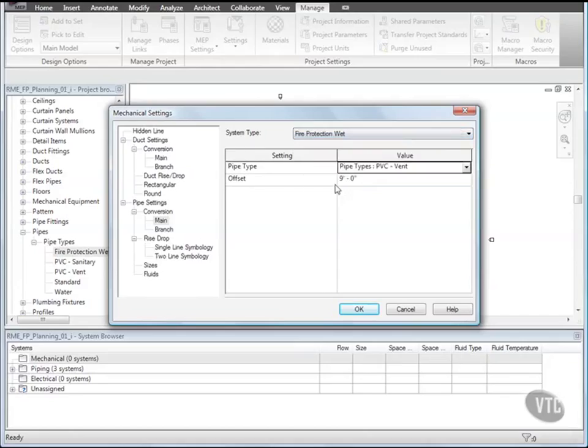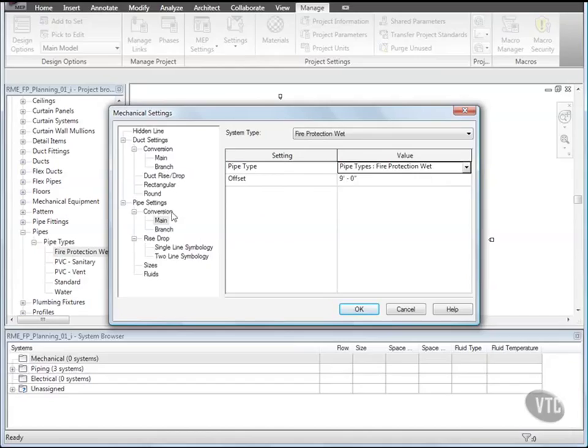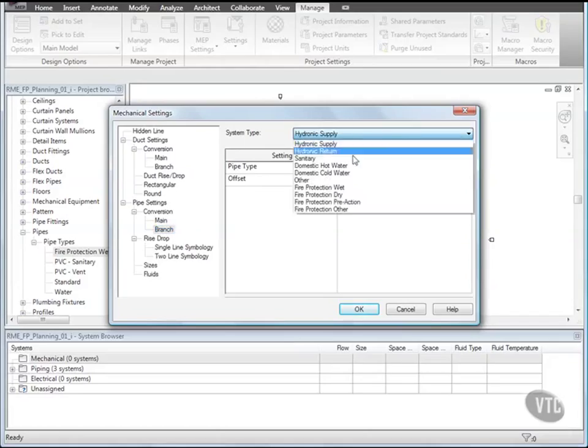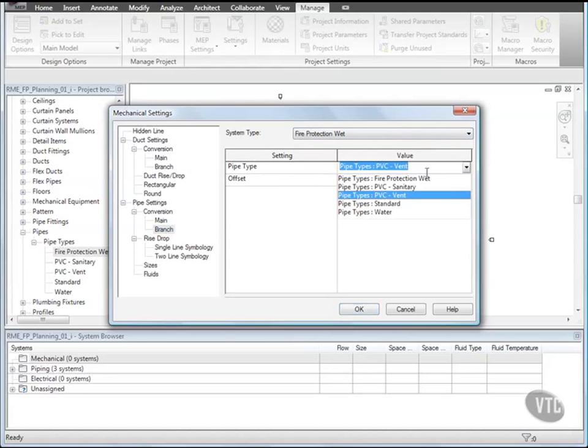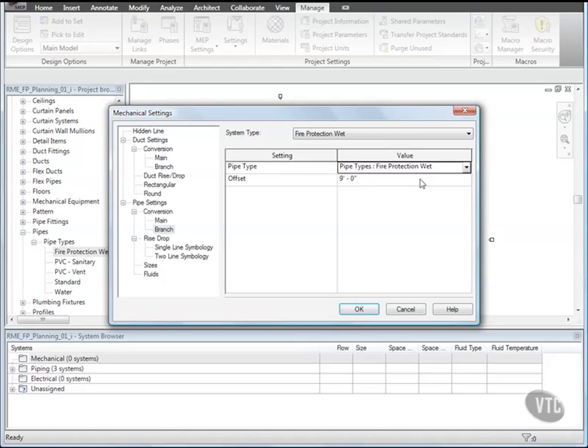And for Pipe Type, on the left side under Pipe Settings, Conversion, select Branch. And for System Type, select Fire Protection Wet. And for Pipe Type, select Fire Protection Wet, and verify the Offset is at 9 feet.